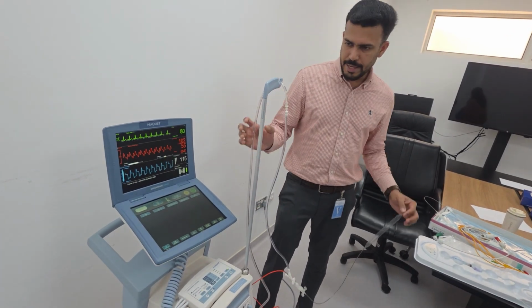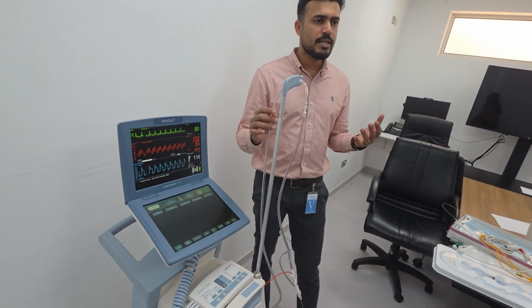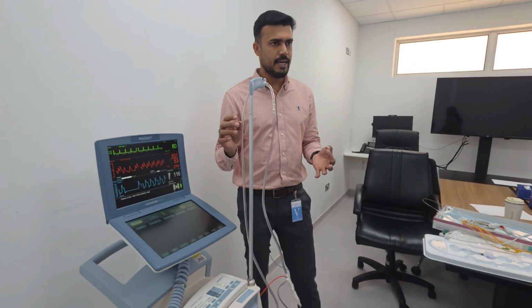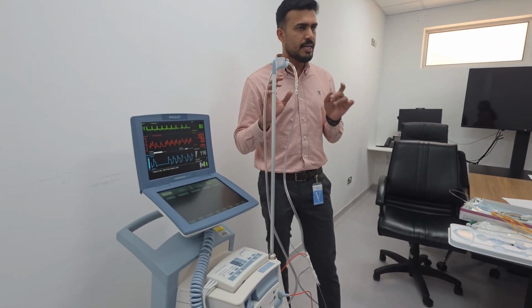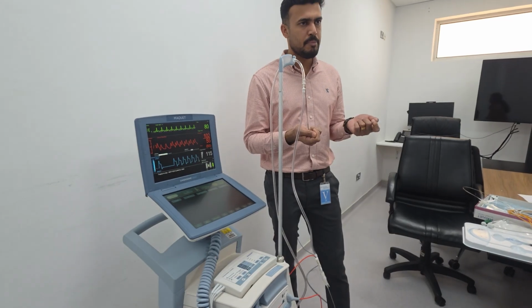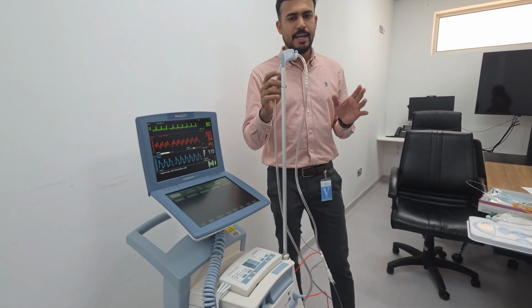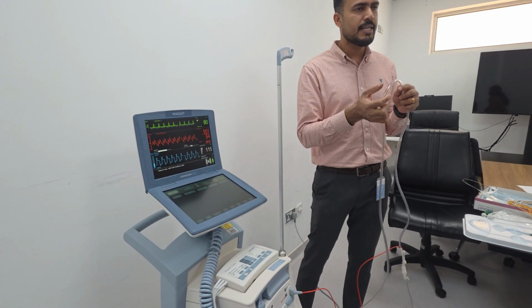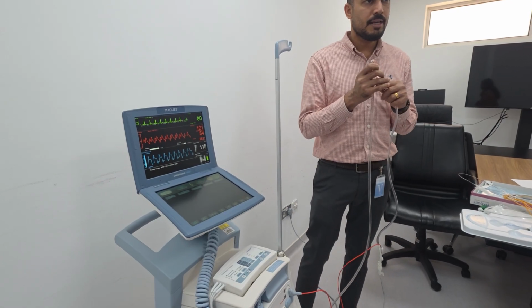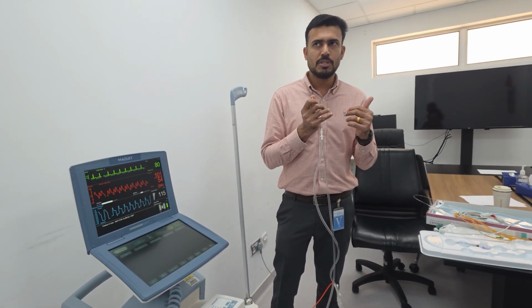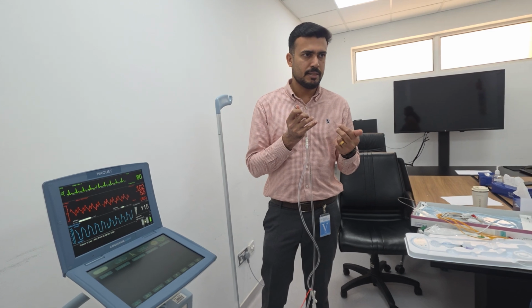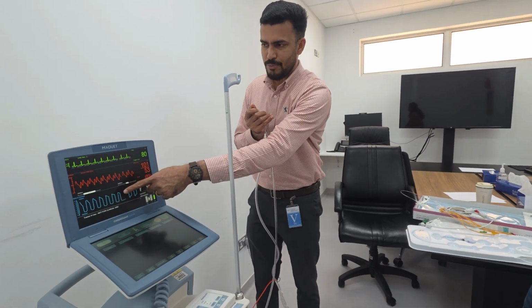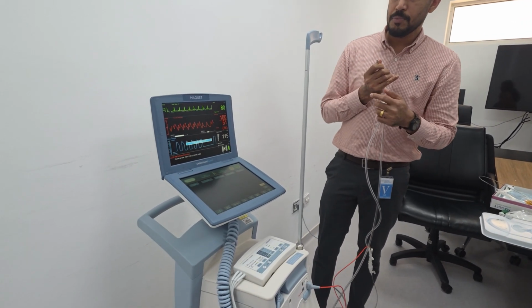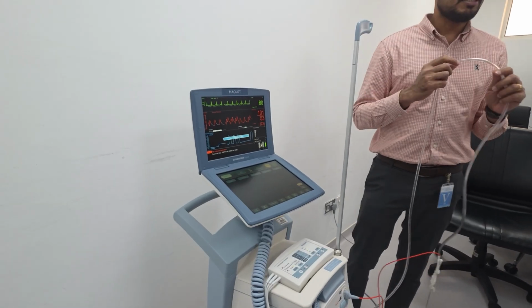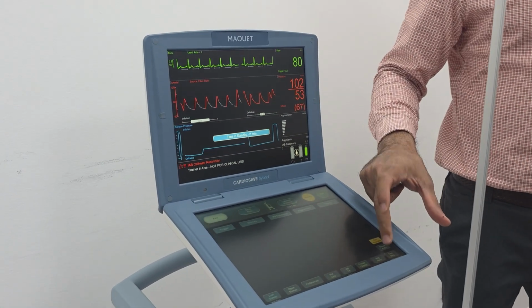In the previous model there was a helium leak alarm, leak in IABP circuit. Here the name is changed to gas loss in IABP circuit, but the meaning is the same. I cannot create the gas loss, but we can create a kink alarm. In the previous model it gave you check IABP catheter if there was a kink, and you could see it in the balloon waveform. But here it will give you catheter restriction. I'm sorry, I cannot create a leakage alarm.